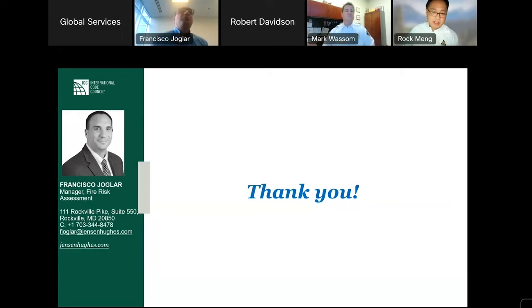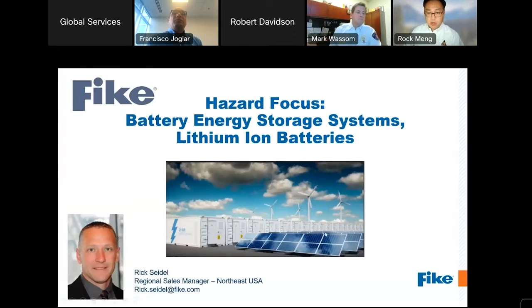So the hazard risk analysis is very critical. It's actually required by both the IFC and NFPA 855. It basically makes sure nothing is overlooked, to minimize any risks that could arise. The risk assessment, along with operations and maintenance documents, is also required to be made accessible to emergency responders. I just want to mention that.